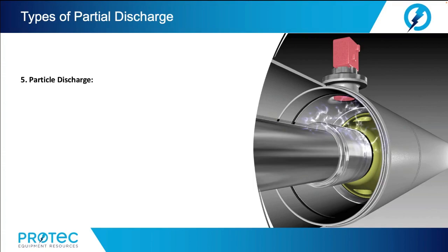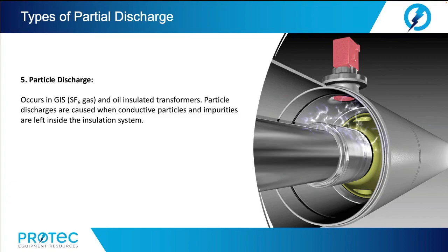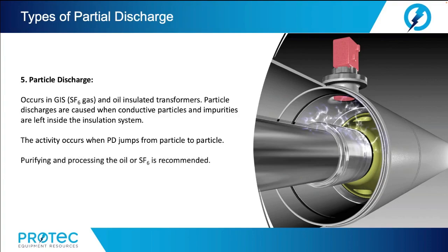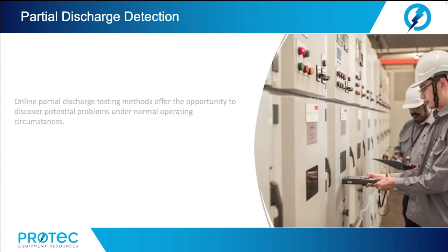And finally, number 5, particle discharge. This occurs in GIS, SF6 gas, and oil-insulated transformers. Particle discharges are caused when conductive particles and impurities are left inside the insulation system. The activity occurs when partial discharge jumps from particle to particle. Purifying and processing the oil or SF6 is recommended.